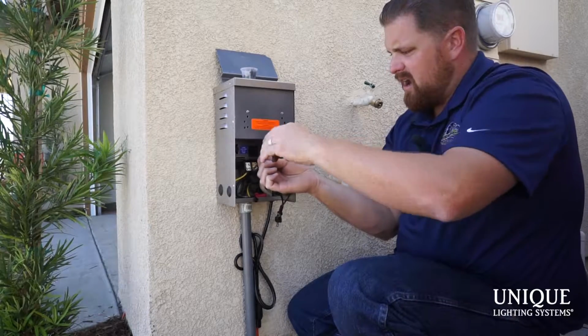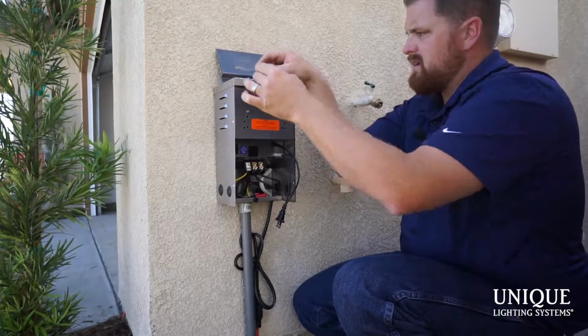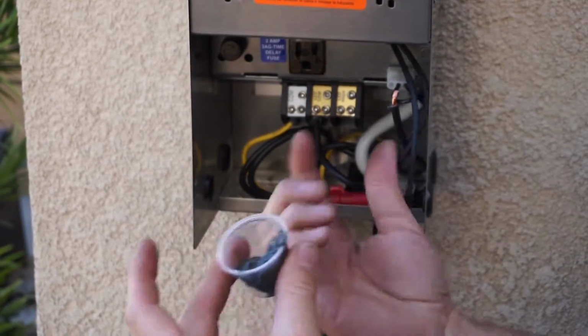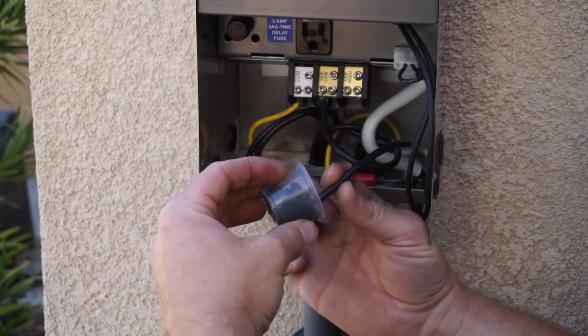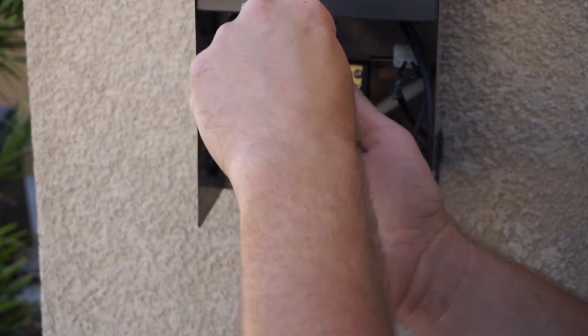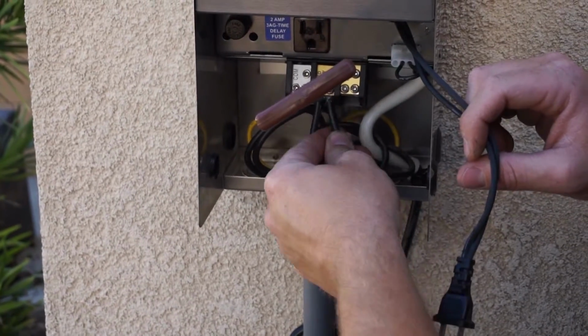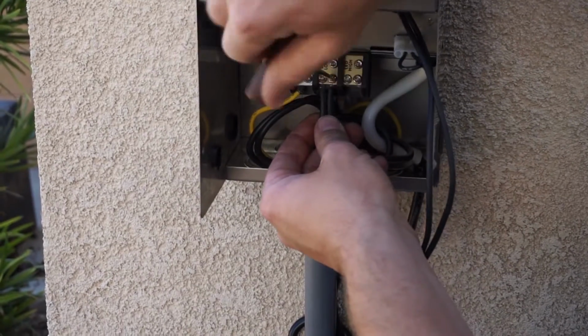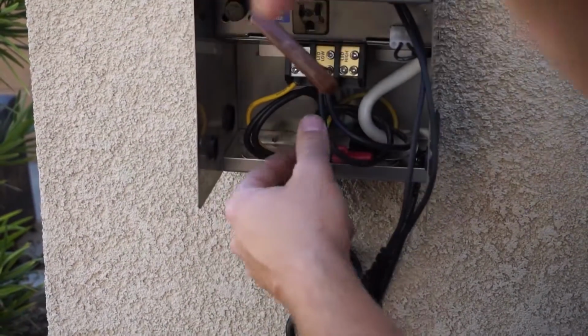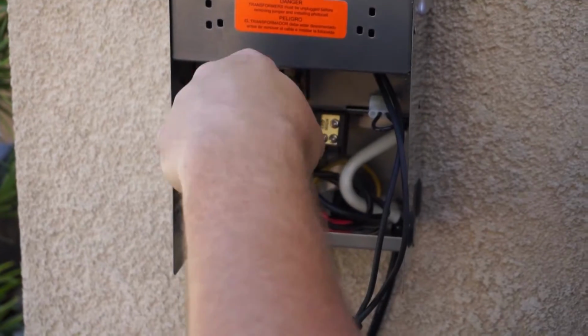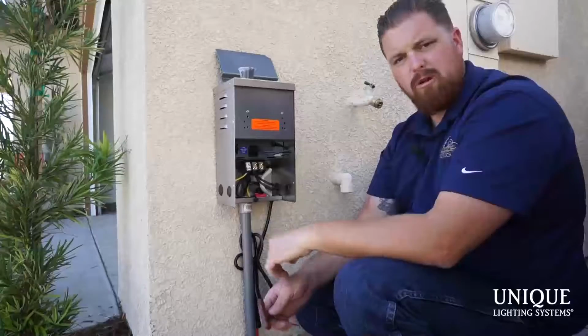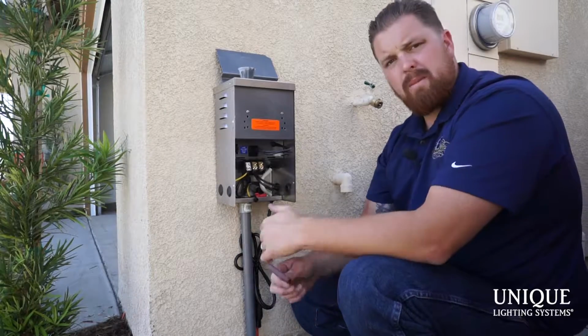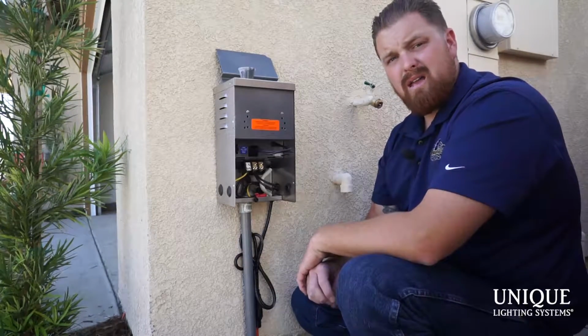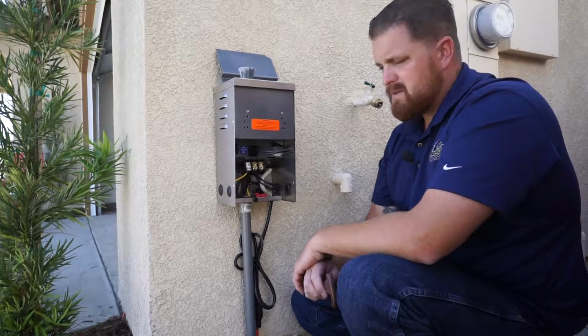And the grease is to prevent any oxidation happening to the wire. In the case if you have moisture in the air, especially coastal locations, you get a lot of that salt in the air, and this is going to prevent anything from happening to this wire. If you notice, I'm not being afraid of putting a lot of grease in there. So got quite a bit of grease. If anything, it just helps things out. Now the transformer is ready to go. Next is going to be programming a Light Logic LPCU A module to this transformer. So stay tuned, and that's what's next.